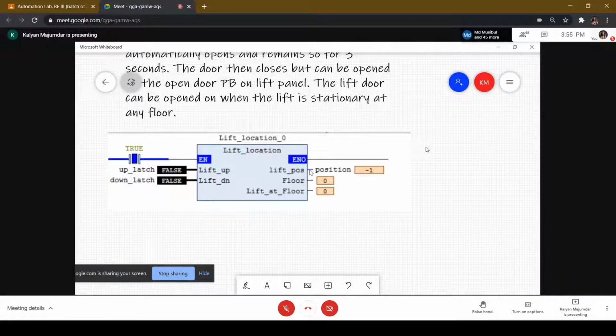This position range depends on the size of your screen - in my case it's 0 to 300. If lift up and lift down are both 0, the lift position remains fixed, meaning you're not providing anything to the up counter line or the down counter line. So the count value remains fixed, and that becomes the position of the lift.